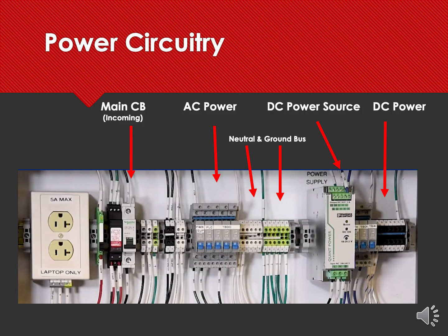Okay, let's talk about the incoming power side of the industrial control panel. Now you'll see there's a red arrow under the main circuit breaker. The arrow is pointing at the only energy isolating device in the whole enclosure, and that is the main circuit breaker. So if you were going to lock out this panel for whatever reason, that would be your lockout point, the EID in the system. Now let's be clear on something. This particular panel just has 120 volt single phase power coming into the panel. And that's the reason for the single breaker that you see.